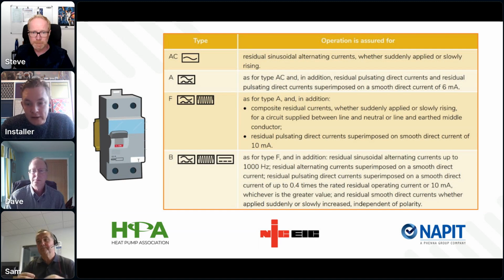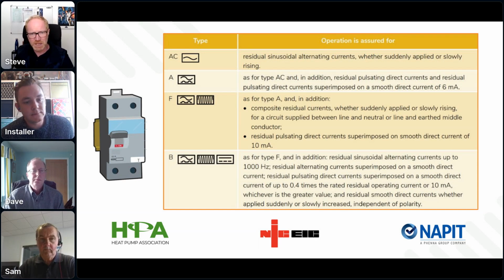Steve, just down on you, because we've had a question about type Bs from Chris. Are we saying that BS 7671 doesn't recognise type Bs? We're not saying that at all, no. BS 7671 recognises all of the devices that are on the screen now that Sam went through. AC, A, F, and Bs. So those are British and European norms that are recognised by the standard.